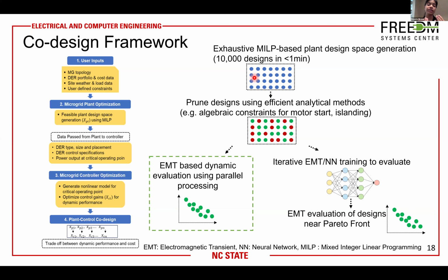It is very computationally efficient, as such a large plant design space can be generated in less than a minute. Then we have fast analytical checks just by adding some algebraic evaluations, and we prune this design space to reduce the number of plant designs we want to evaluate using EMT simulations.